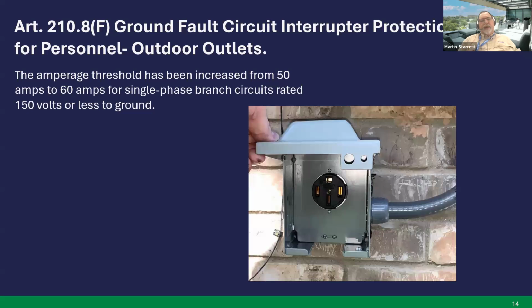Article 210.8(F), ground fault circuit interrupter protection for personnel, outdoor outlets. They did increase the amperage threshold from 50 amps to 60 amps for single phase branch circuits rated 150 volts or less to ground. So if you have an outdoor outlet and it's 60 amps single phase, 150 volts or less to ground, you will now have to provide ground fault circuit interrupter protection. Next slide.